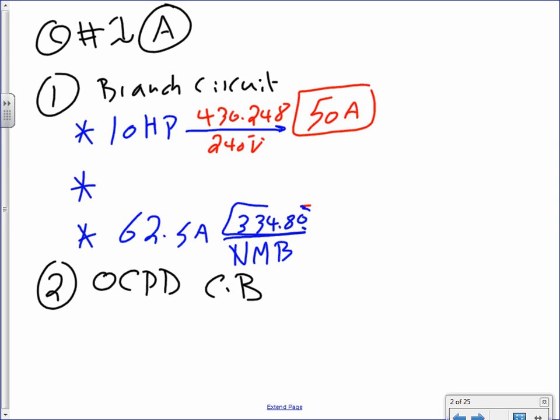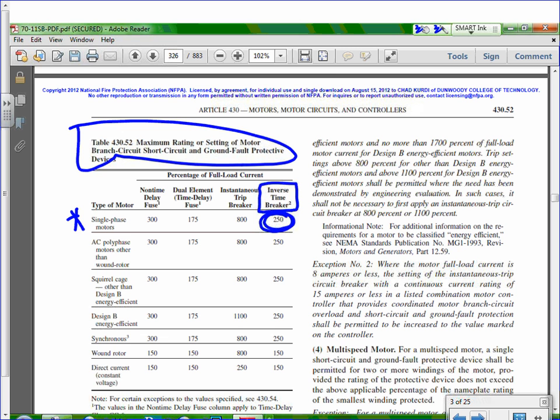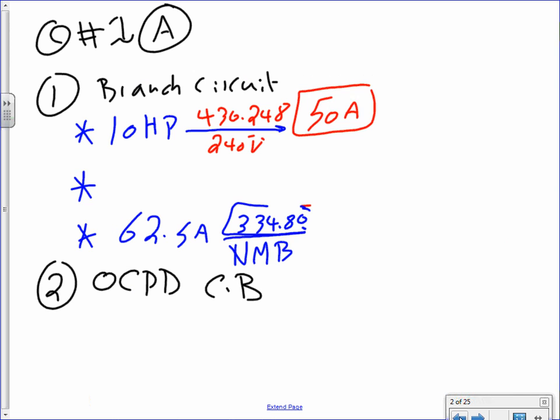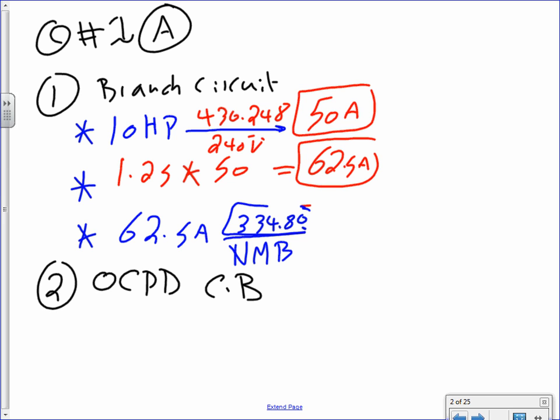And I hope you guys remember. I think I have it here. No, that's not here. Okay, I don't have it. But when you go to table 430.248, you get 50 amps. Then for branch circuits, guys, you use 1.25 multiplied by 50, and that will get you a healthy 62.5 amps. So why do we multiply by 1.25? Because it's continuous load. We multiply by 1.25 because it's continuous load.